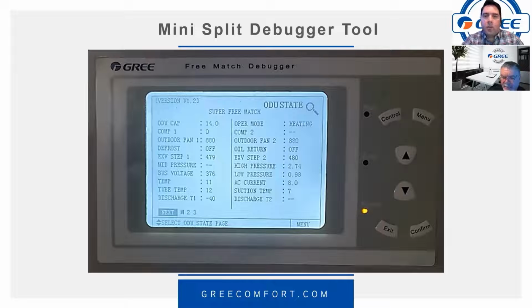Daniel? Yeah, the important thing to me here is that you can see what your temperature sensors are reading, or at least what the system thinks they're reading. So if they're out of the range you're looking for, you can go, okay, let me get my meter out of the bag and check that particular sensor just to make sure it's reading correctly. Right. So it's doing a lot of troubleshooting for you, getting you to the right street, not necessarily the right address, right? Yeah, exactly. But it's helping you dial in so that you do less work, fumbling around trying to check everything independently.